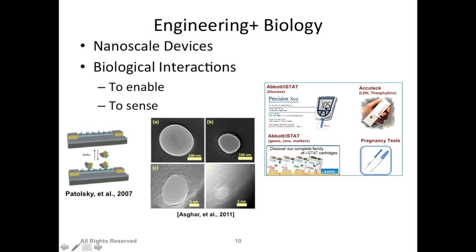It's an ammeter. Means you are measuring the current by applying a voltage, and with the measured current you can then correlate, okay, if this is a sugar level, then this much current you are getting, so most probably this is the sugar level in the blood. And these are normally very reasonable devices, glucose meters, so you see some fluctuation in the results, maybe 5 to 10%, but that is pretty acceptable.